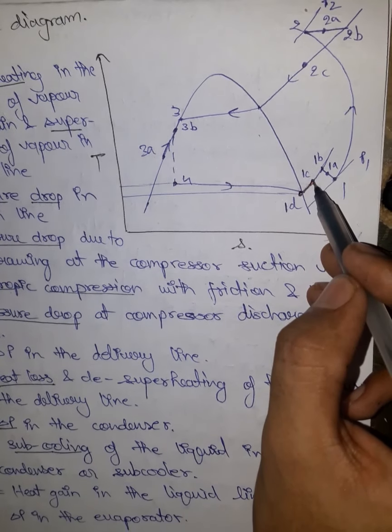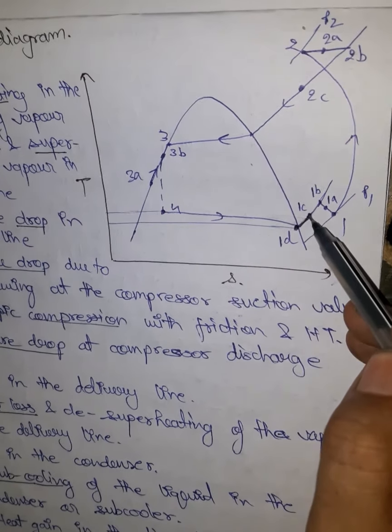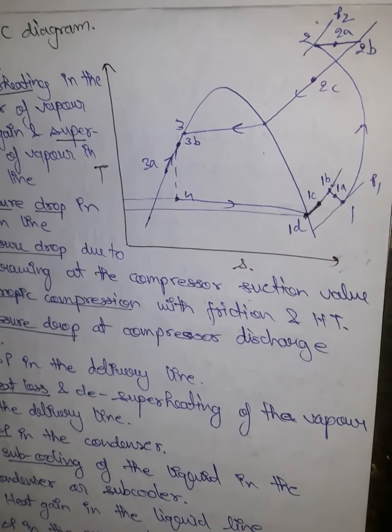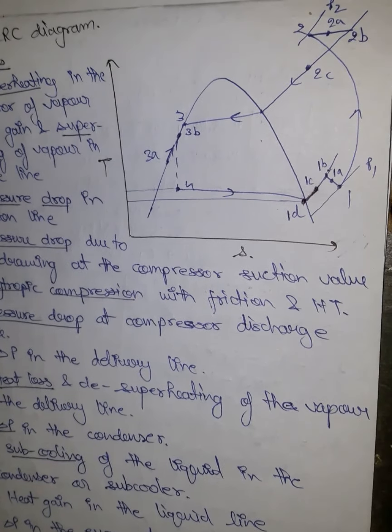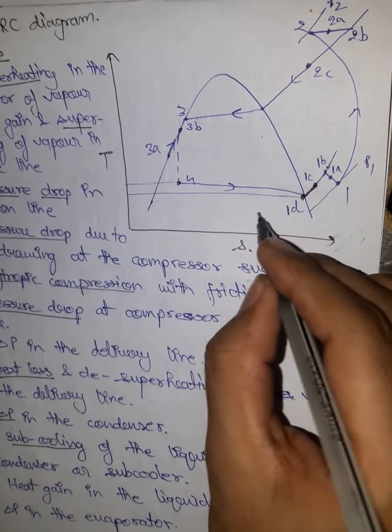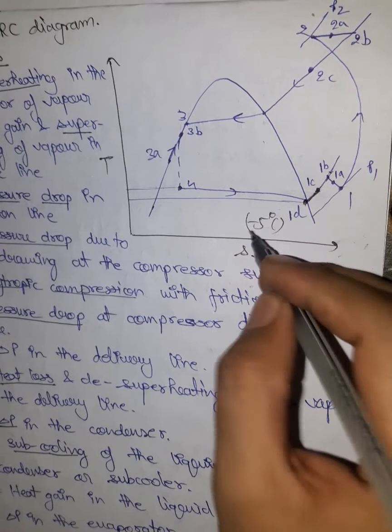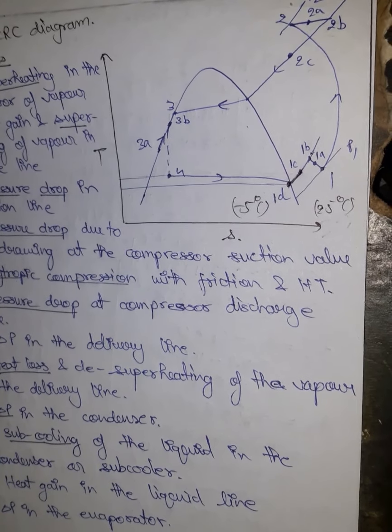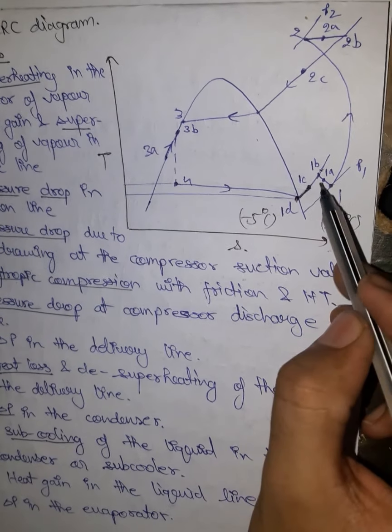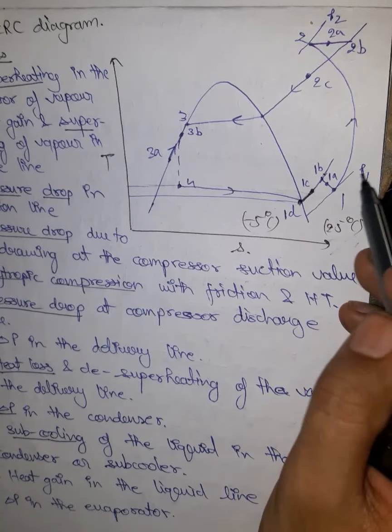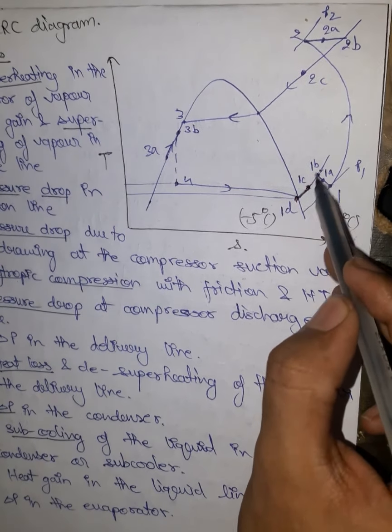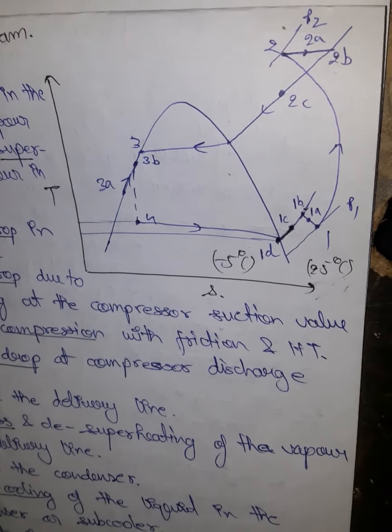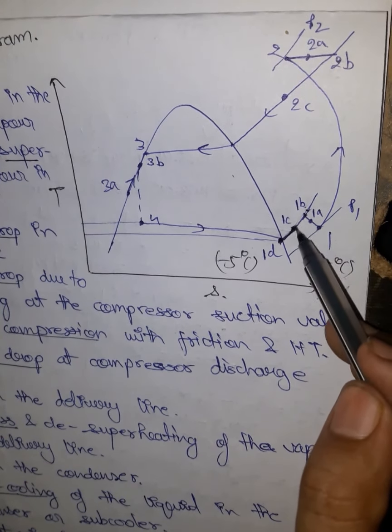From point 1c to 1b, heat gain from the surroundings is occurring because the evaporator temperature is very low and the outside temperature is higher. For example, the evaporator temperature may be around minus 5 degrees Celsius and the outside temperature around 25 degrees Celsius, so heat naturally flows from outside into the suction line — the line carrying refrigerant to the compressor. From 1c to 1b, superheating is happening due to this heat gain.